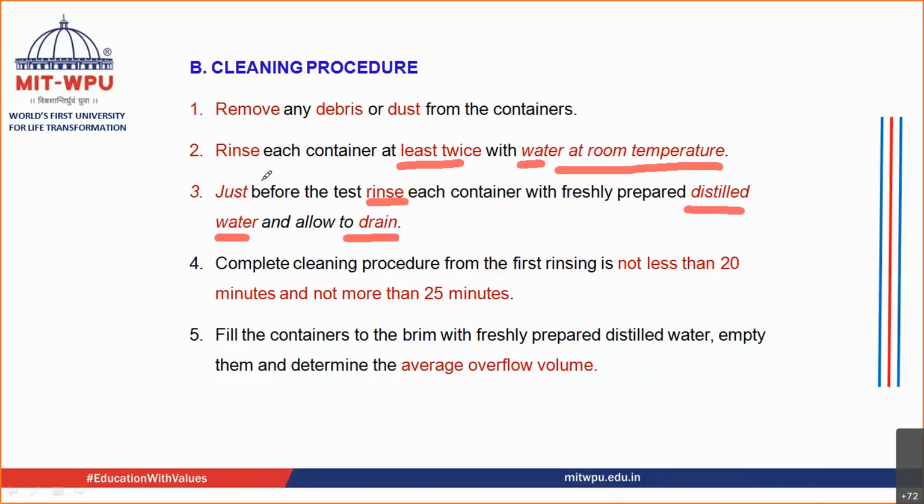Now this cleaning procedure, starting from the rinsing up to the end, should be carried out in not less than 20 minutes and not more than 25 minutes. Why has this standard been given? So that you should not carry out the rinsing procedure in just 1 or 2 minutes and then leave it.